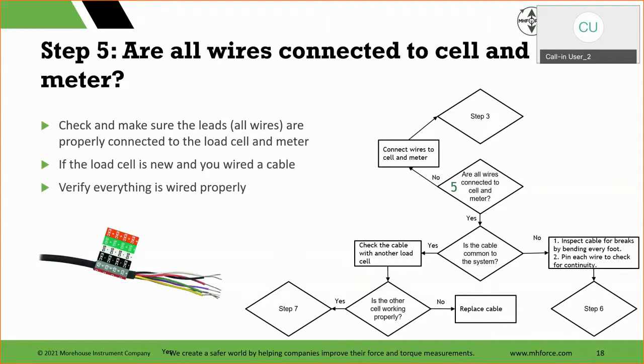Are all wires connected to the load cell meter? This one happens quite a bit, where during shipment something came loose, a back panel might have got smashed, someone might have not packed it properly. So what we're just going to do, this is another visual type inspection, and then we're going to get the multimeter. So we're going to first check and make sure all the leads, all wires, are properly connected to the load cell meter. If the load cell is new and you wired the cable, verify everything is wired properly.